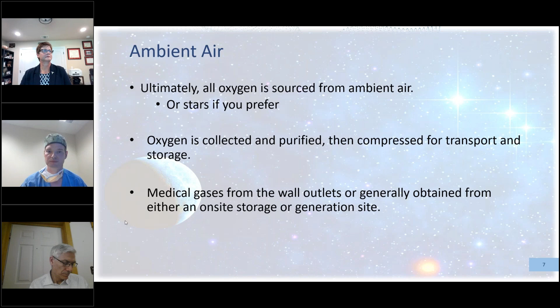So for larger facilities, what you'll find is that many of them will use compressed oxygen in the form of liquid oxygen. They'll have a very large tank that will have liquid oxygen in it, and then that's slowly allowed to evaporate to feed the central supply lines. Going beyond the topic of oxygen, but also just your other medical gases, air is generally, in larger hospitals, compressed by an on-site compressor that'll take the ambient air, purify it, run it through some filters, and compress it up to the 50 psi that you're going to get out of your wall outlet. And then for the anesthesiologists like me, we always want to know where our nitrous oxide is coming from, and that's almost exclusively gotten from tanks, usually in some form of a tank manifold.